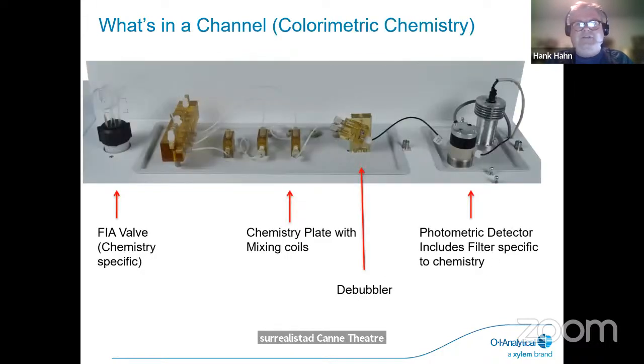Here's a breakout of the colorimetric chemistry by a side view. So if you're using a chemistry that requires flow injection, we do have the FIA valve, your chemistry plate. It's got the mixing coils, air teas, whatever necessary for that reaction. In the segmented flow, we have a debubbler. We remove the bubble before it does enter the lamp. There we have the photometric detector, which includes the filter specific to the chemistry. The lamp is easy to replace. It sits right on top of the one detector cell right here, and with 2 set screws, you can take that out and easily replace that.